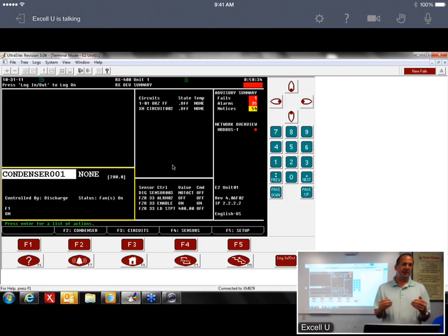Over the course of those 6 seconds, if you're at 50% valve capacity, it's going to be open for 3 seconds and closed for 3 seconds. If it's at 100%, it's going to be open for the entire 6 seconds. If it's at 0%, it's going to be closed for the entire 6 seconds. That's what the valve percentage stands for.